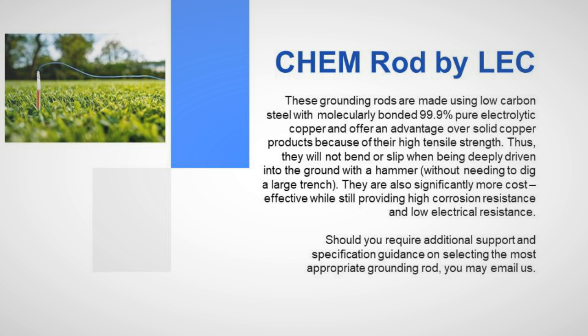Chem rod by LEC: these grounding rods are made using low-carbon steel with molecularly bonded 99.9% pure electrolytic copper, offering an advantage over solid copper products because of their high tensile strength. They will not bend or slip when being deeply driven into the ground with a hammer, without needing to dig a large trench. They are also significantly more cost-effective while still providing high corrosion resistance and low electrical resistance.